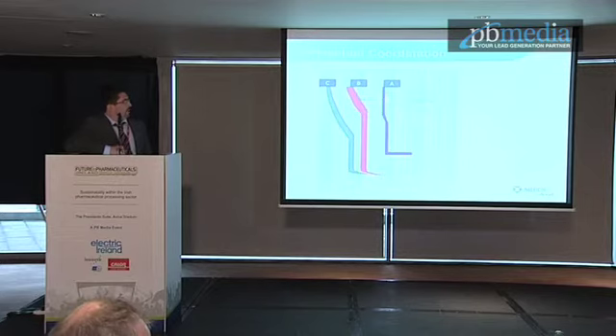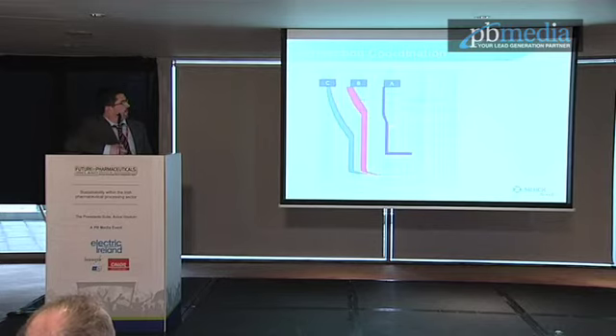So this is how protection coordination should look. The 3 graphs here are lined up beside each other. If these graphs were crossing over at any point, it would mean that the fault wouldn't be cleared at the point of fault, it would be cleared upstream, which would have a much larger impact on the facility.